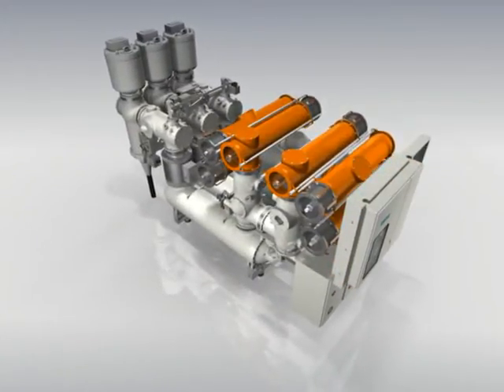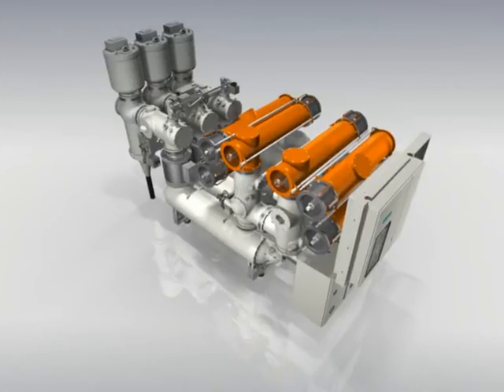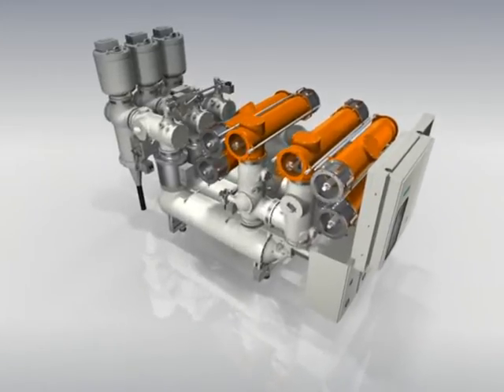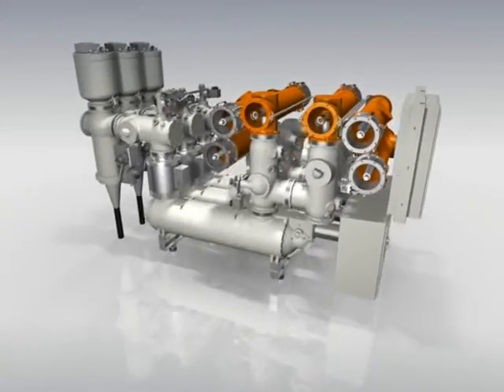Passive busbar modules without any electrical and mechanical activity guarantee reliable operation and make busbar failures more than unlikely throughout the entire lifetime of the switchgear. Furthermore, during extension or maintenance works, at least one busbar remains in service.